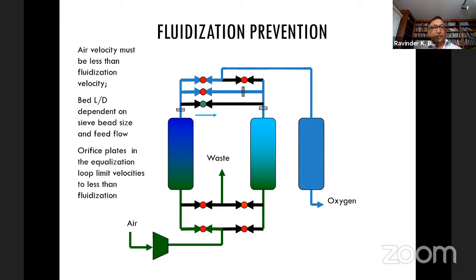So to protect against fluidization in the upward direction, it is a question of selecting a good diameter for the vessel. And the second thing, when we are depressurizing it, there are 2 times when you have potential fluidization. One is when you are pressurizing the vessel, and the second is when you equalize, you open a large valve, because you have very small time to equalize the bed. And when you're equalizing it, there are flows upward in this vessel, but there are flows downward in the other vessel. And if you have an equalization rate which is very high, it will end up crushing the sieve here. So you need to make sure that you don't crush this. So what we do is we add some flow restricting devices. And that's called flow restricting devices here. You size the valve like that. So that's how you prevent the fluidization.